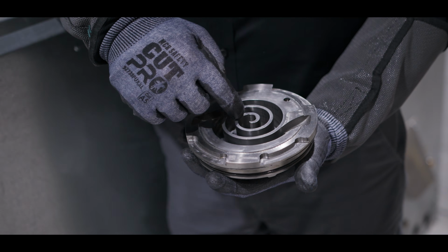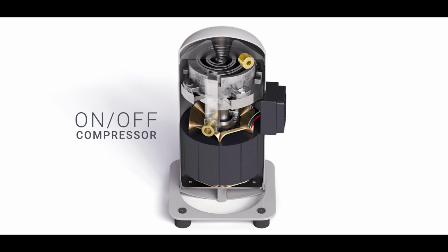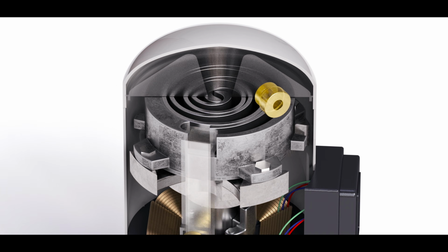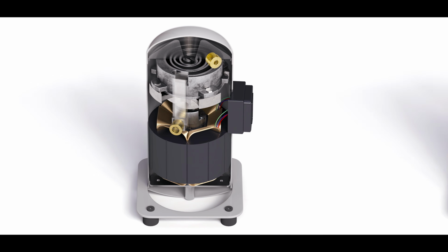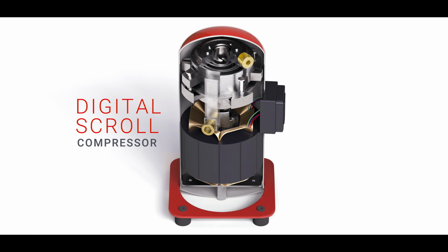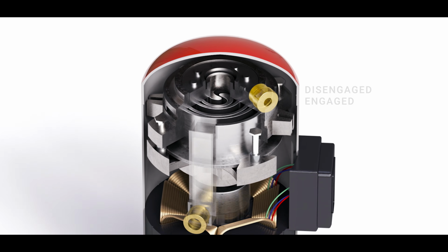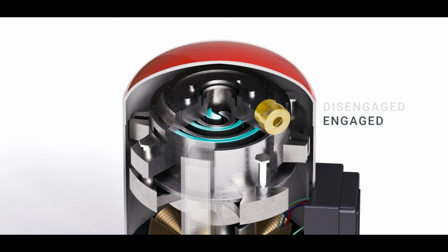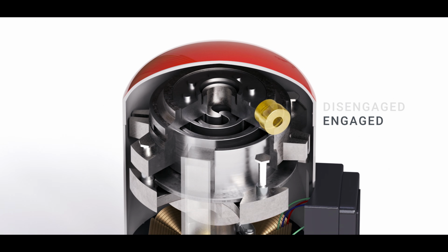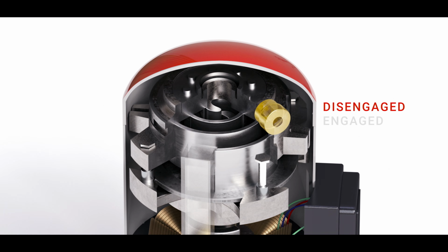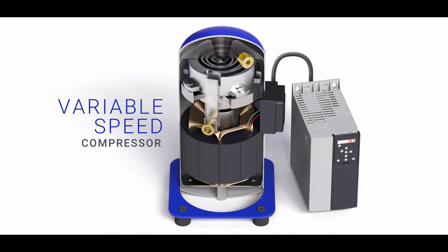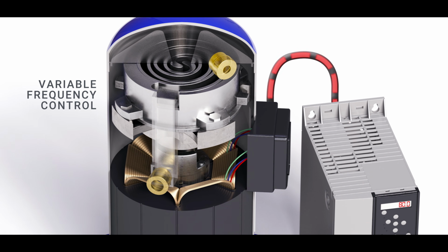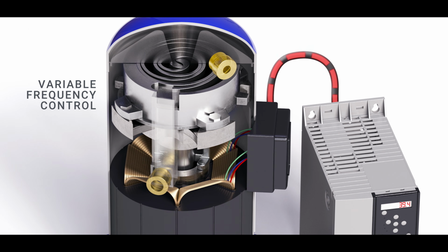For the compressors, we had three options. There's your on-off compressor, right? That just, you send power to it, it runs at one speed. You take power off, it shuts down. Then you have your digital scroll compressors, where these compressors always have power, and they just disengage the compression scrolls at various rates. By doing that, you can change the amount of refrigerant flow. This is more efficient than on and off, but it's not as efficient as actually slowing down the compressor, varying the speed of the compressor to achieve the desired refrigeration flow rates that were needed for your design.